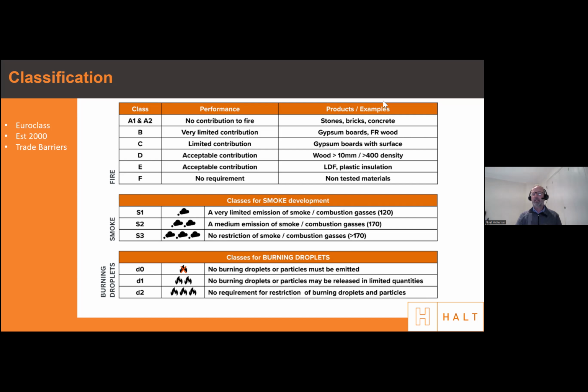A1 and A2 are generally regarded as having no contribution to fire. One of the key differences for this standard compared to BS 476 is that it looks a lot more at the timber itself - it looks at the reaction to fire of the product you're using in construction.